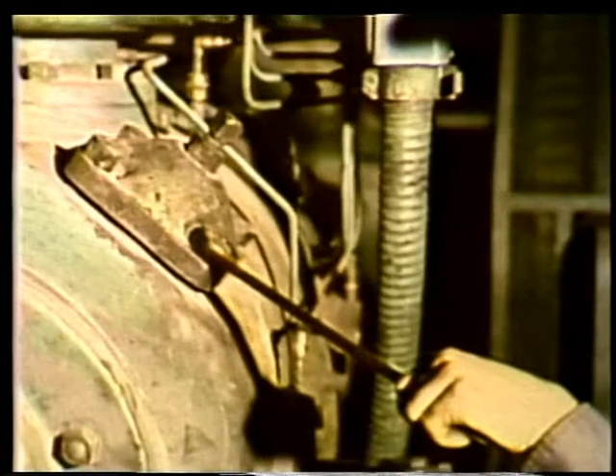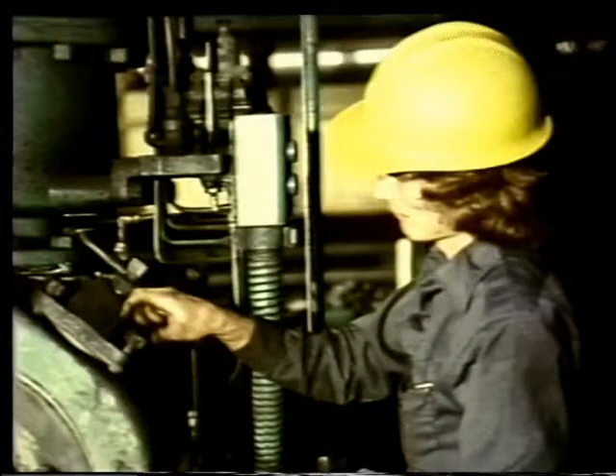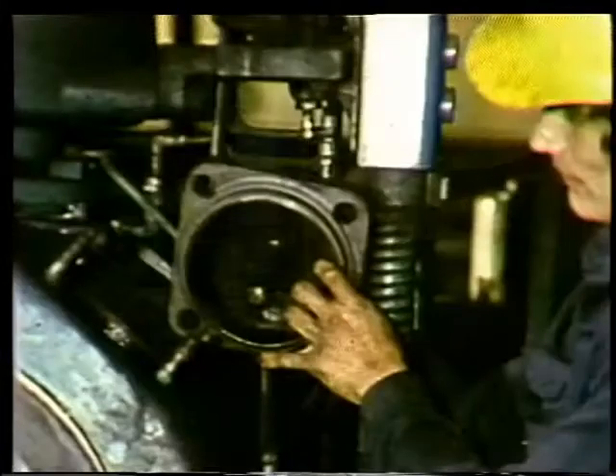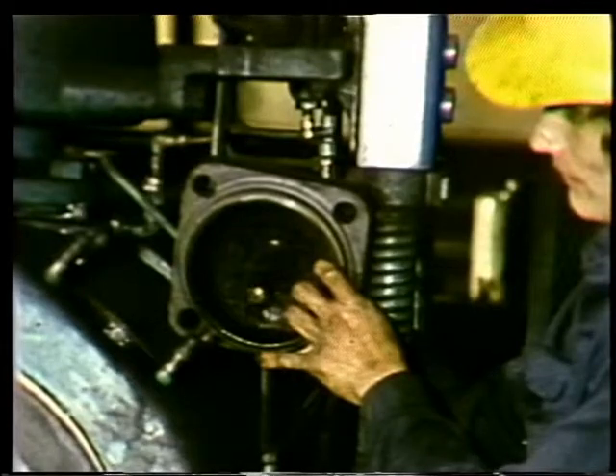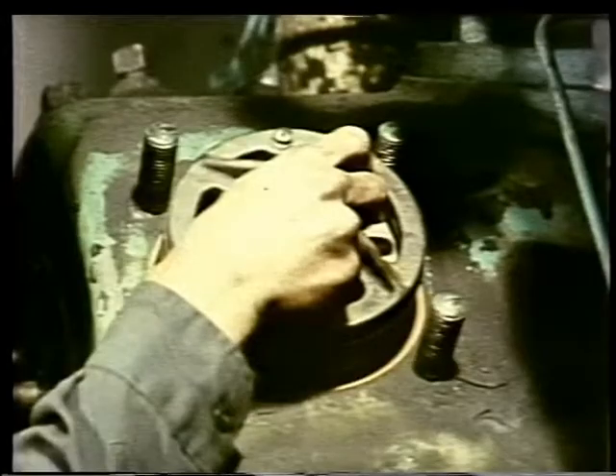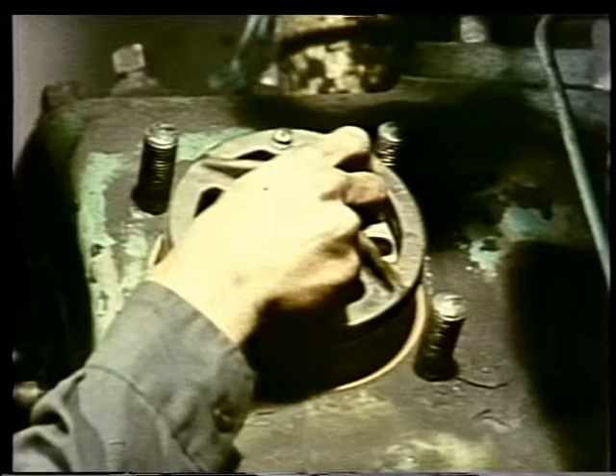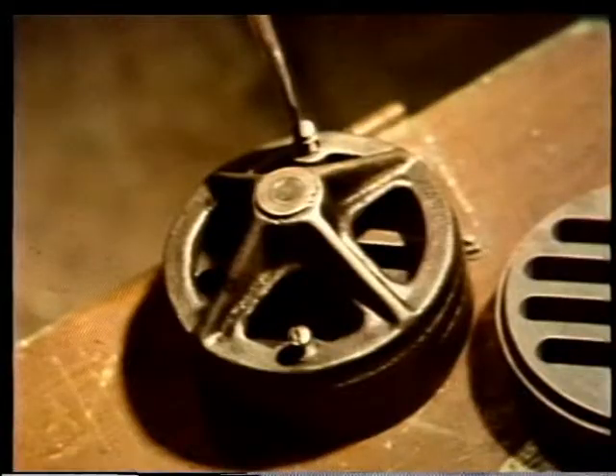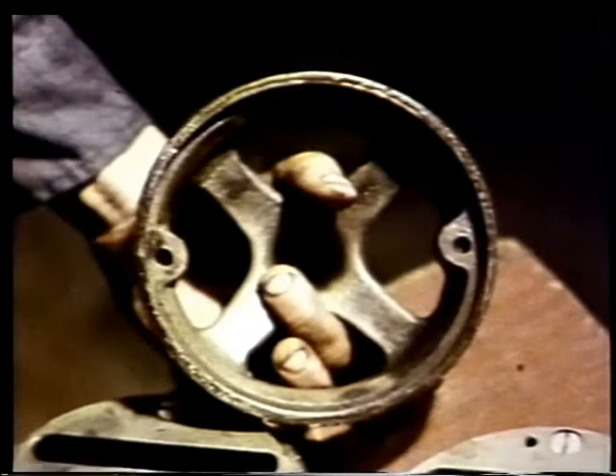First, to remove the valve, you have to break the nuts holding the outer cover free and remove them from their studs. When the last nut's been removed, lift the outer cover off and set it aside safely out of the way. Next, lift the valve out and remove the gaskets. The inner cover is fastened to the valve by two screws. After you remove the screws, you're ready to take the valve apart.